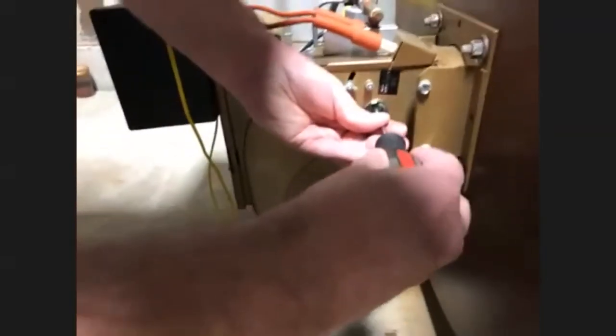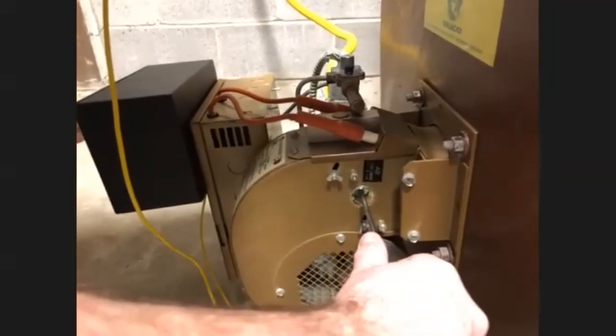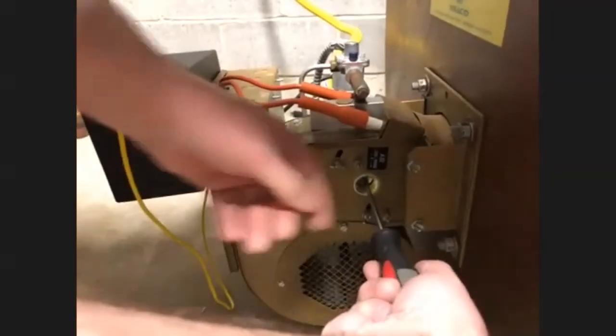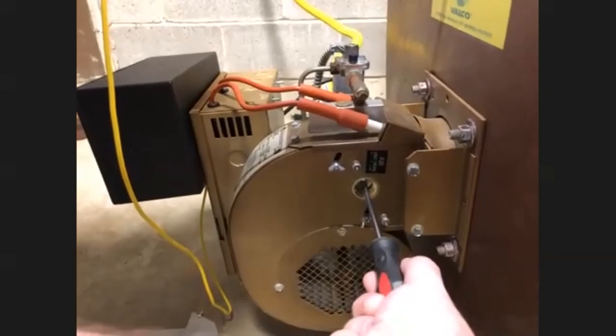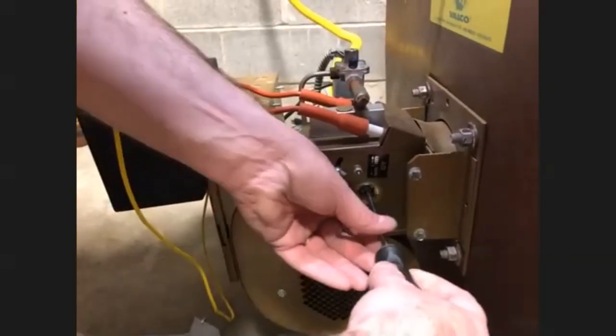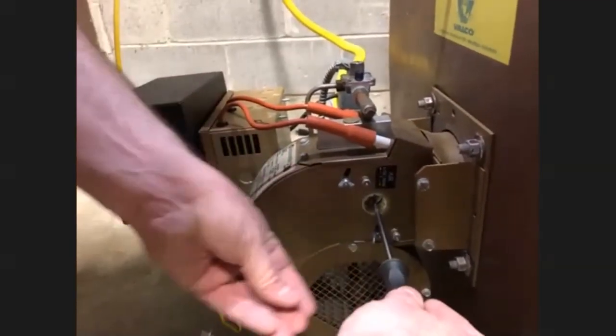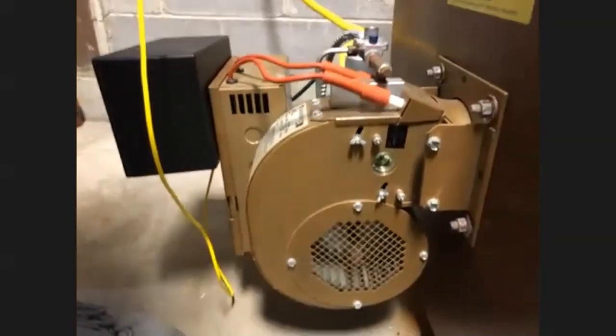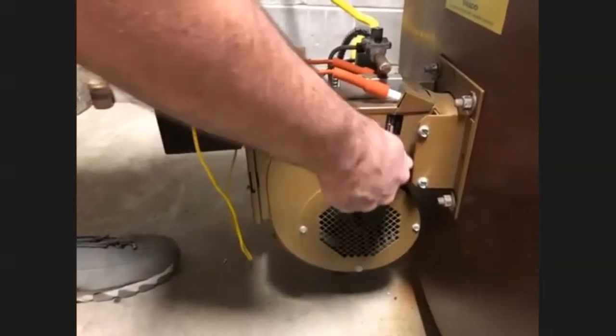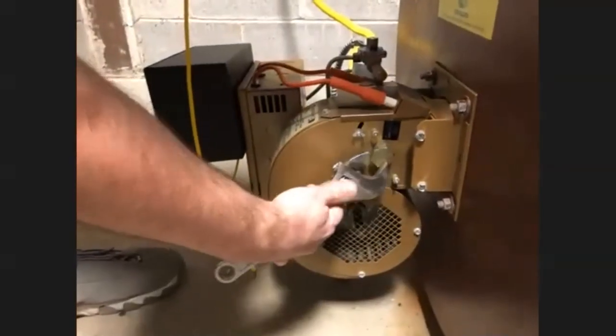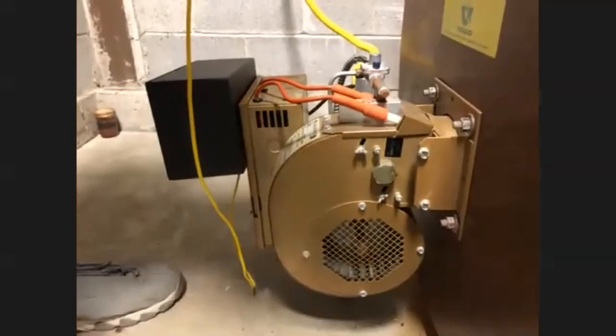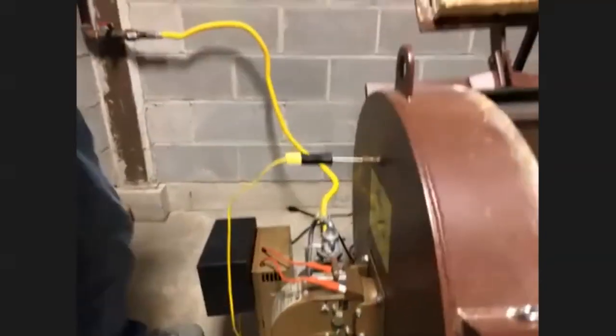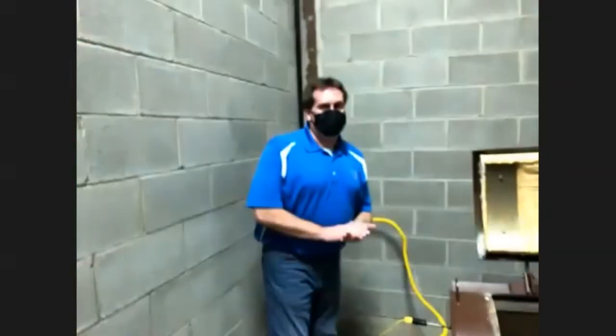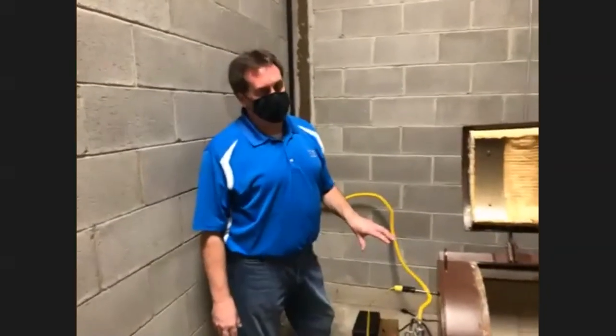So I'm going to take a screwdriver. And what you need to do is, after you have that adjustment known, you fully close the screw. You turn it clockwise completely. Now you want to count how many turns you want to go backwards counterclockwise to set your setting. So I wanted 1.5. So there's one. I have 1.5 settings. Once you have that applied, you can go ahead and close that back up. Now you should be set for the proper size, the proper BTU rating for this particular model. Again, you must do that with all gas cremators, whether it be natural gas or propane. That must be adjusted before you do regular operation.